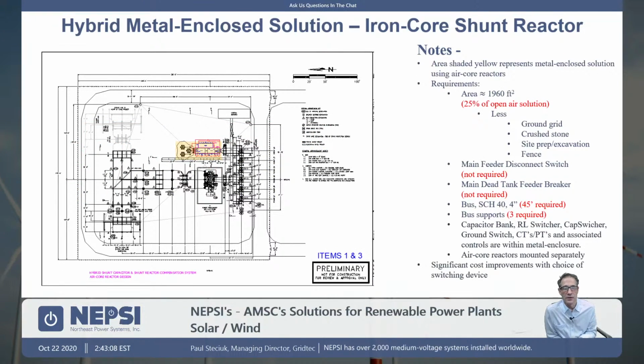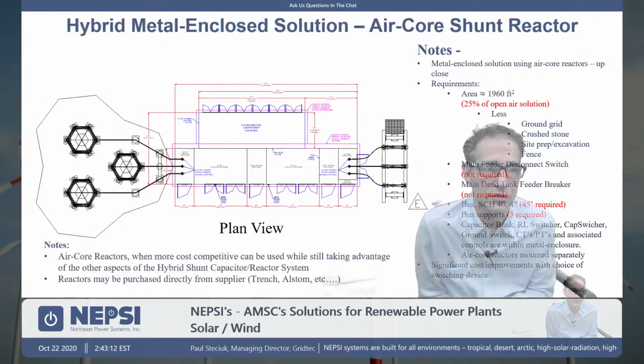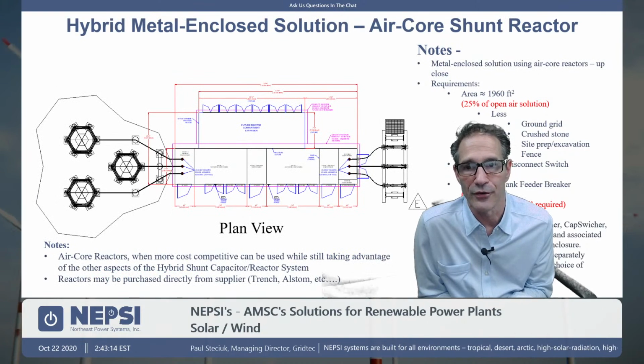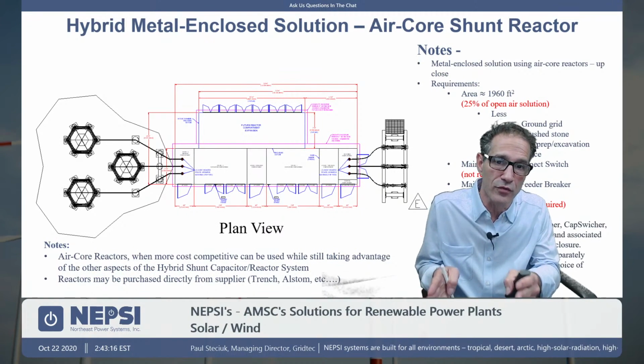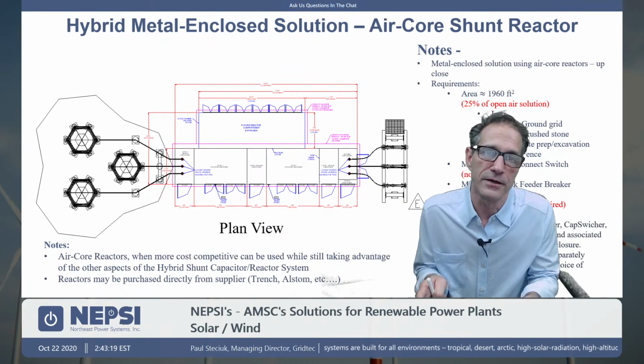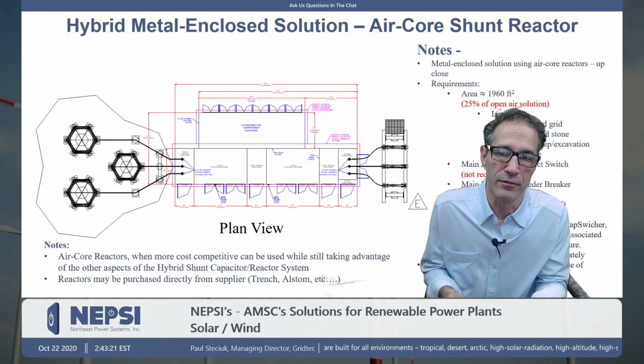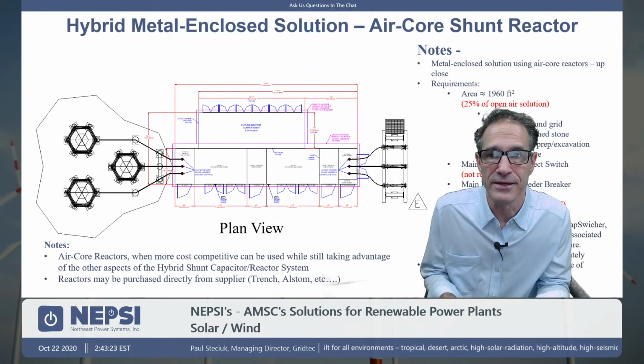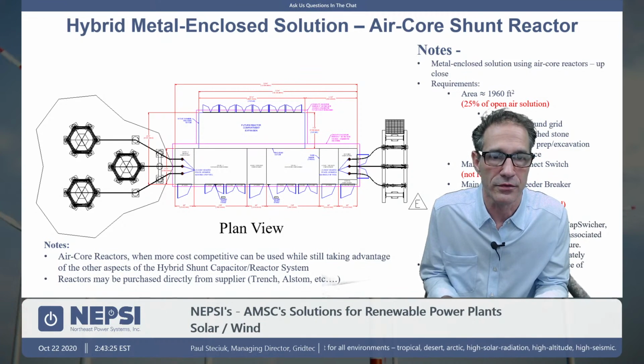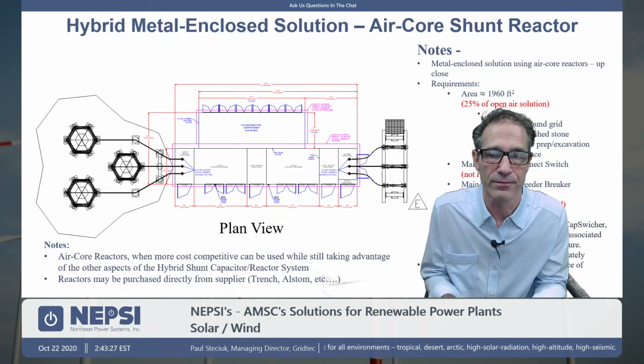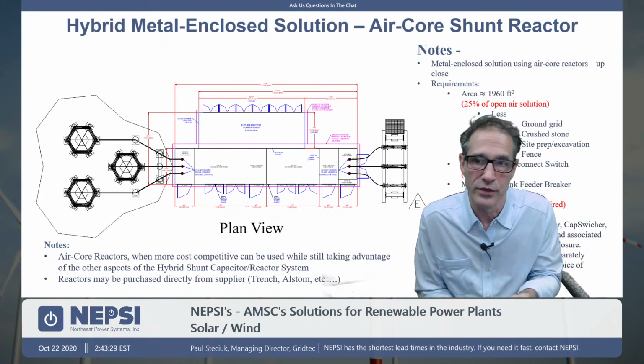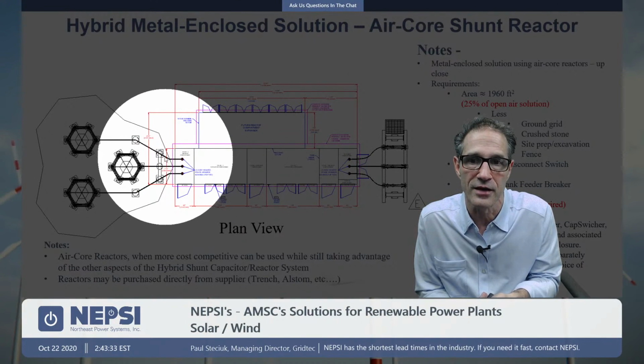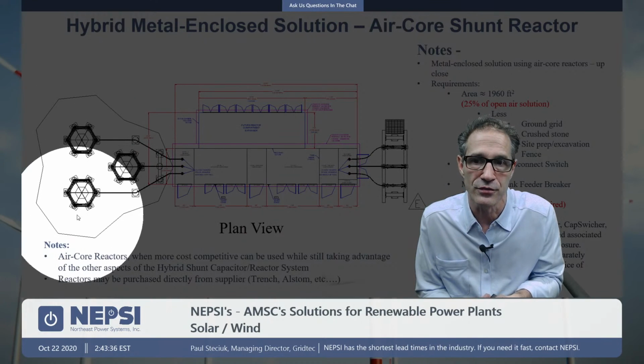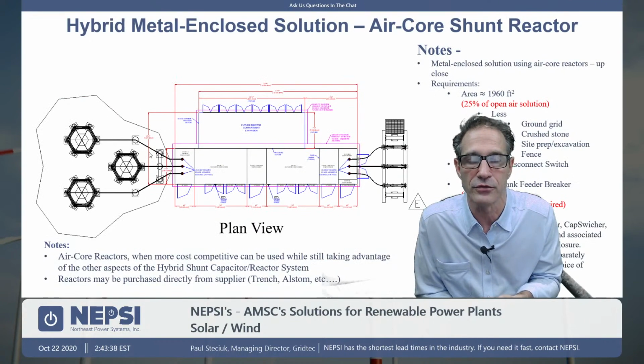And we decided that when doing these drawings, we would also show how it looks if we use air core reactors. So remember, we have a crossover point for shunt reactors. If you get above that, say 5 MVAR range, maybe air core reactors is an avenue you want to explore. So in this case, we did a set of drawings and we put roof bushings on the exit to go out to a shunt reactor bank that is air core reactors.